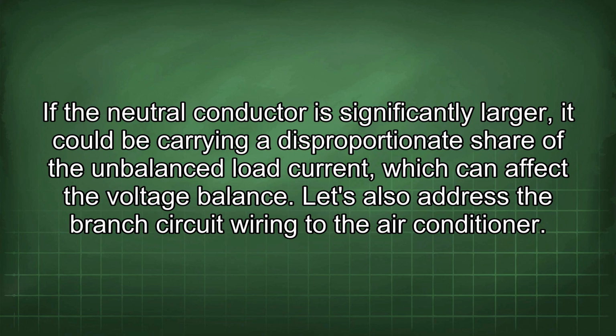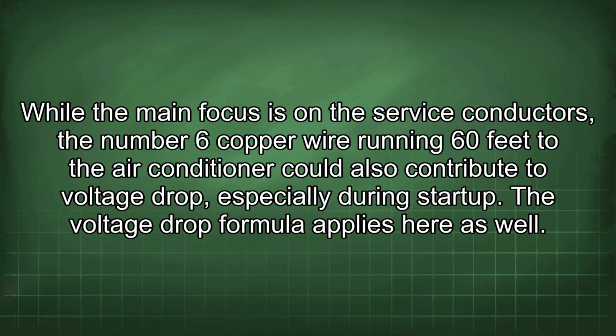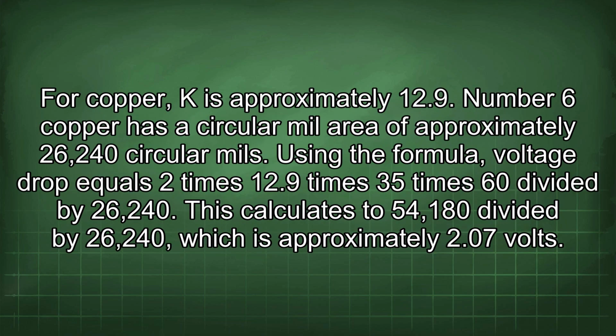Let's also address the branch circuit wiring to the air conditioner. While the main focus is on the service conductors, the number 6 copper wire running 60 feet to the air conditioner could also contribute to voltage drop, especially during startup. The voltage drop formula applies here as well. For copper, K is approximately 12.9.